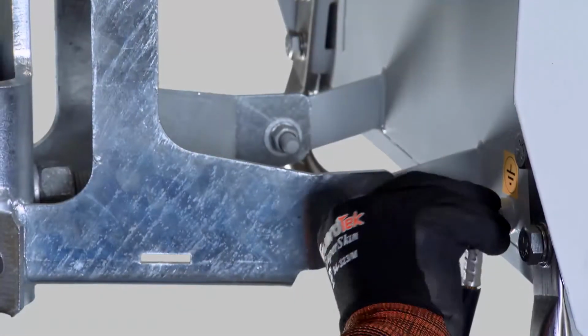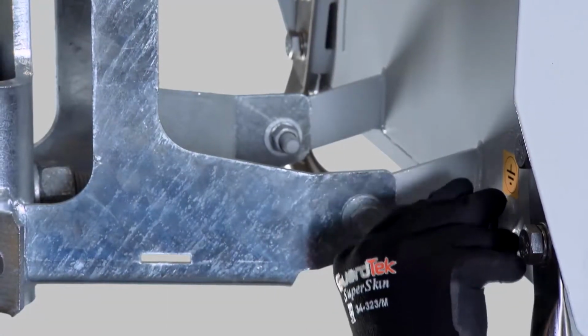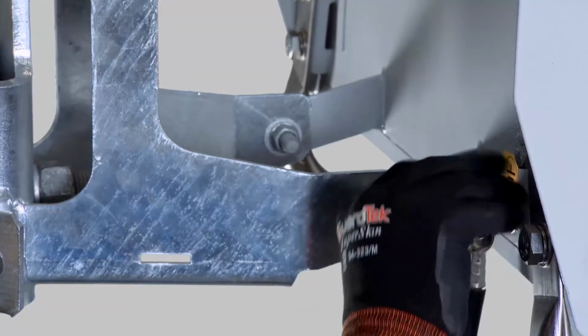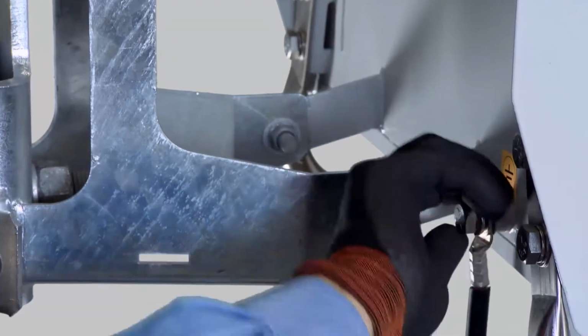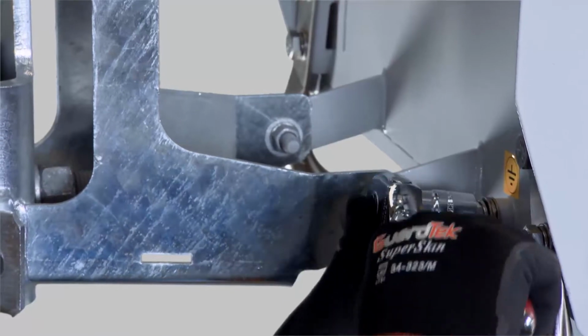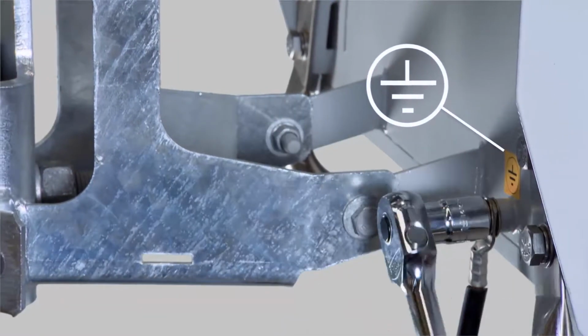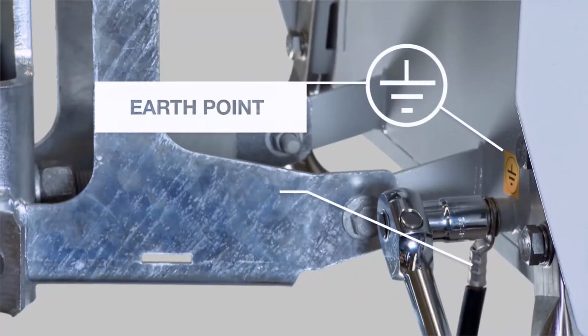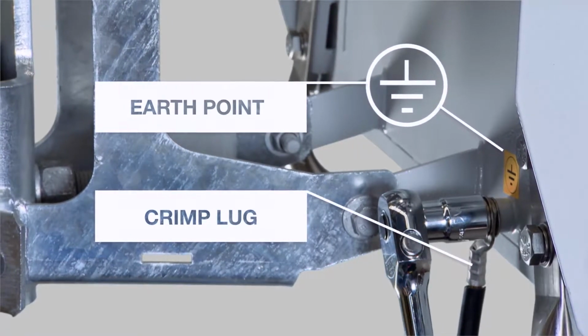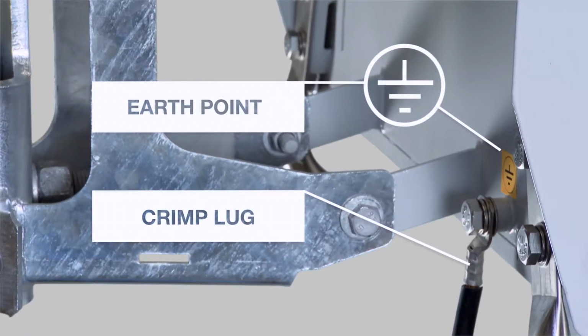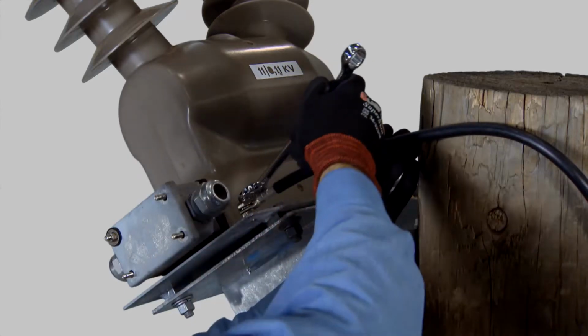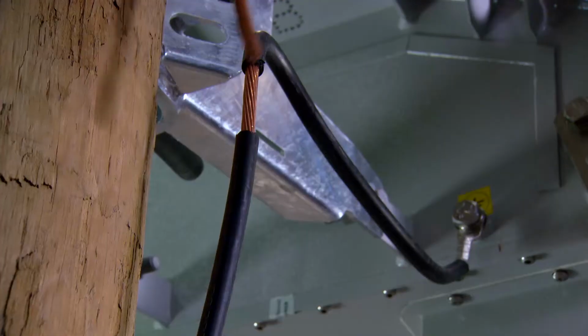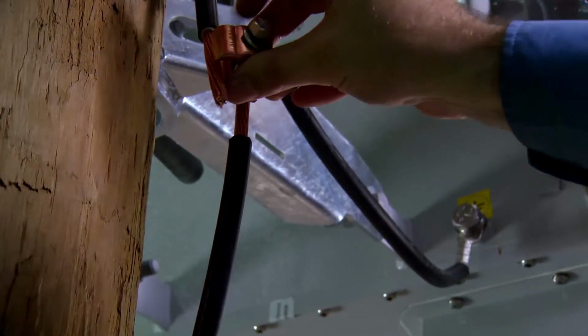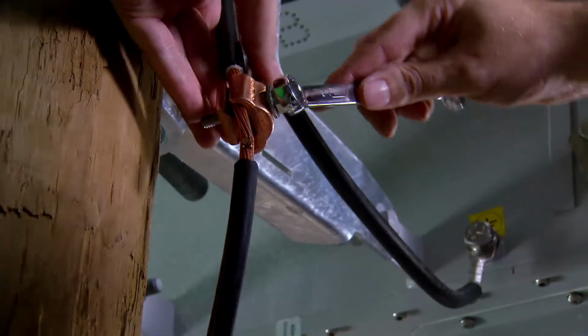Good earthing is required for operator safety and to protect the recloser from damage. NOJA Power specifies a 35mm squared copper conductor for the earthing material. Crimped lugs should be used, and connections to the tank, VT and cubicle must be to the marked earth points. Connect the VT earth to the main earth cable using a short length of 35mm square cable and a line tap. Secure the cable down the pole.